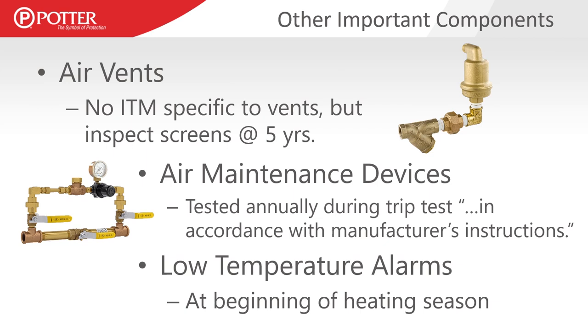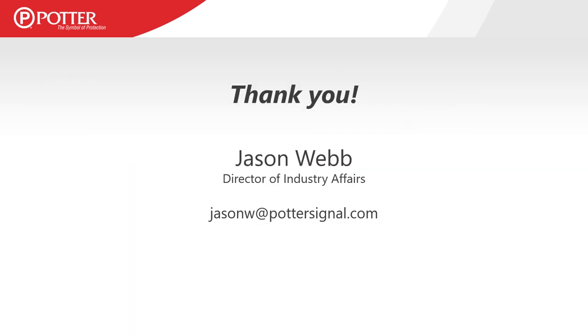Low temperature alarms — as we touched on earlier — are important for verifying the temperature in a dry pipe valve enclosure is above freezing. Low temperature alarms are required to be tested at the beginning of the heating season. All these requirements can be found in manufacturer's data sheets, NFPA 25, and NFPA 72. There are lots of different tasks and frequencies, but it's important that we take care of these devices because they are the ones monitoring or supervising these systems and in some cases helping them activate, as in a pre-action system.